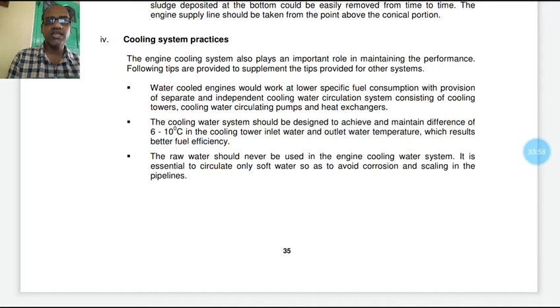The cooling water system should be designed to achieve and maintain a difference of 6 to 10 degrees between the cooling tower inlet water and outlet water temperature, which results in better fuel efficiency. The raw water should never be used in the engine cooling water system. It is essential to circulate only soft water so as to avoid corrosion and scaling in the pipelines.